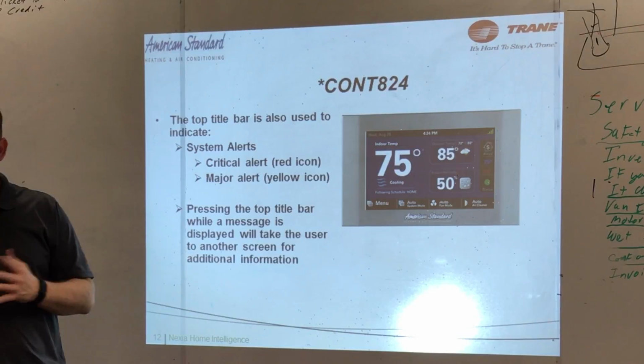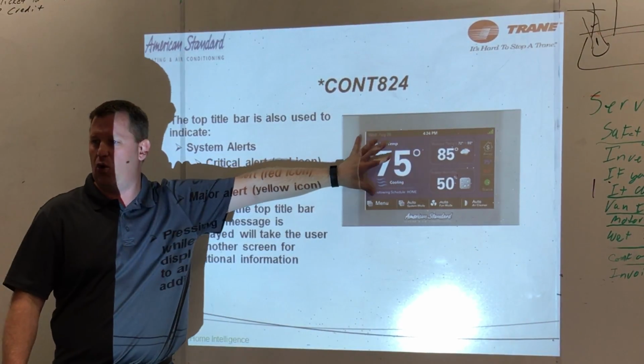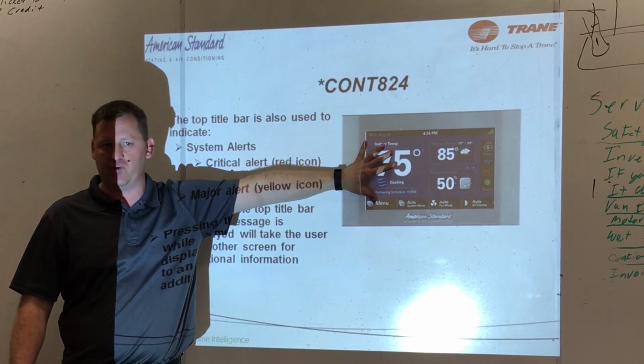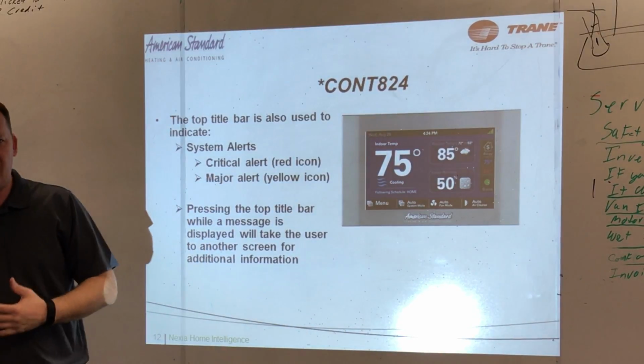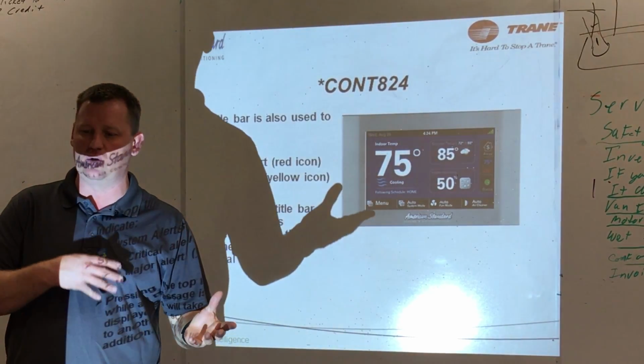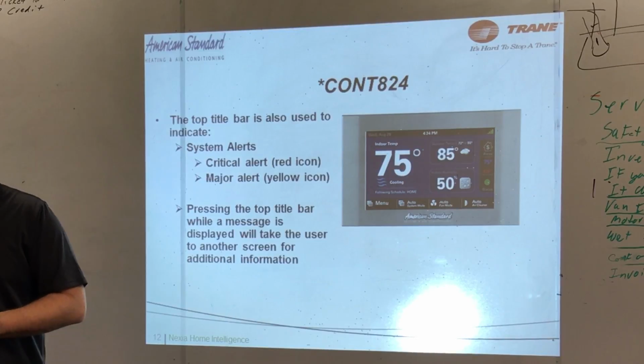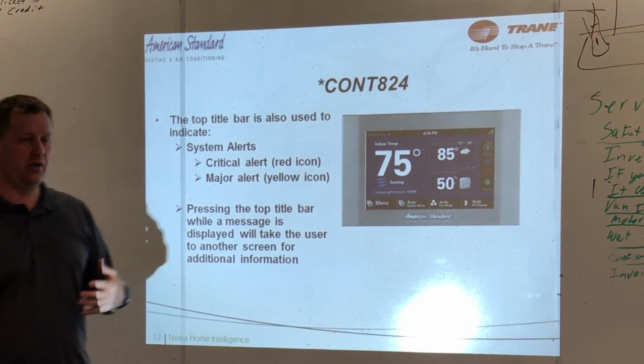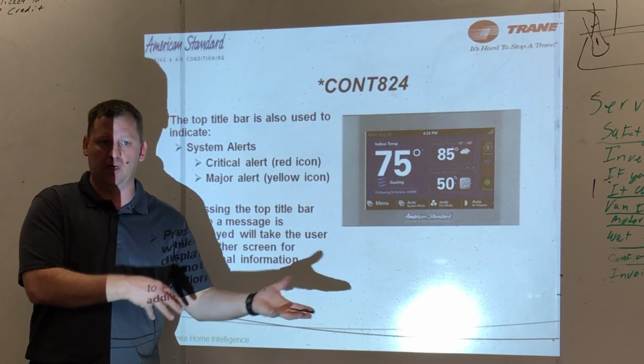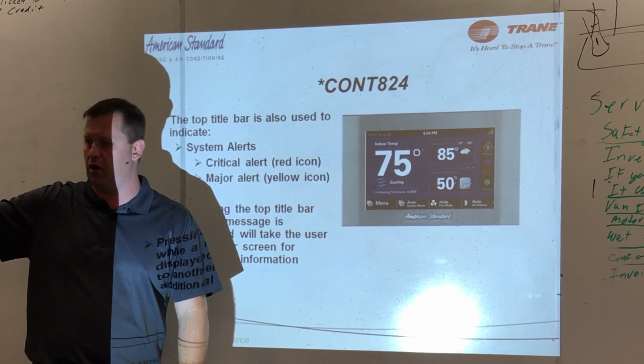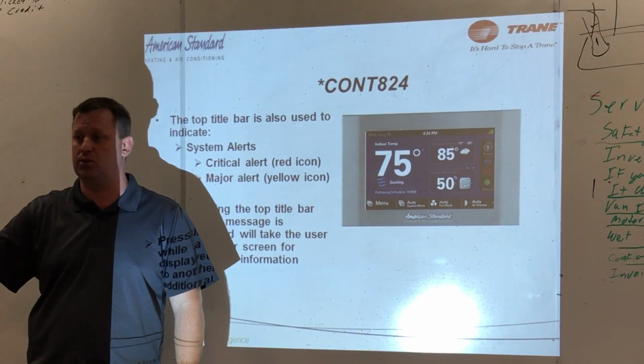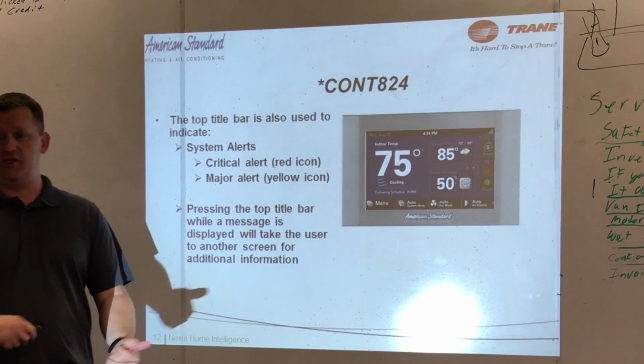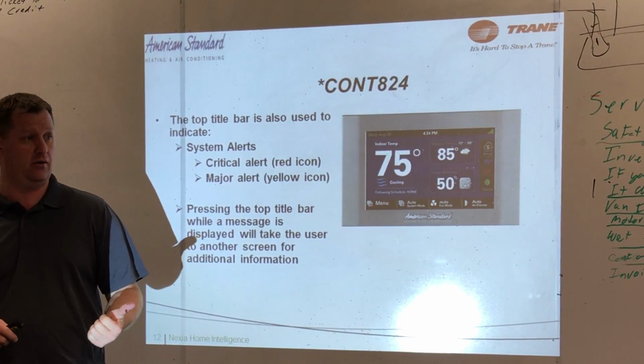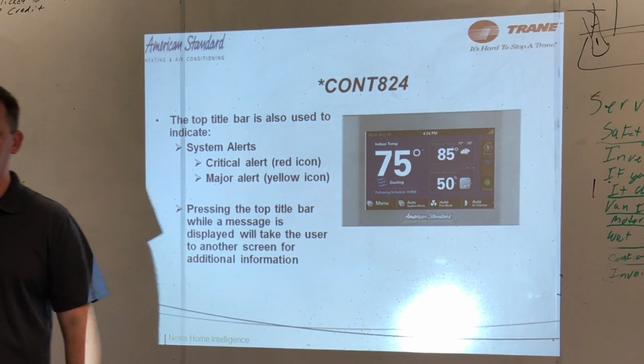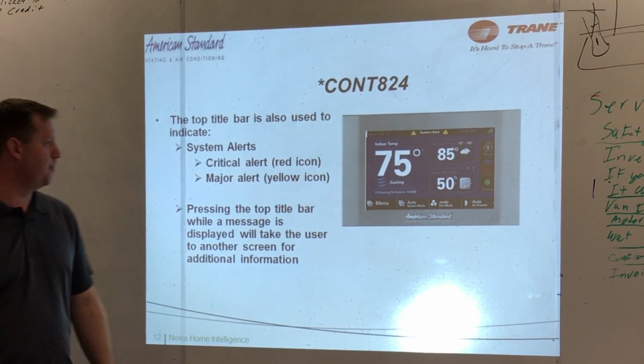With the 824, because it's not communicating, we don't have a whole lot of alerts we can really have. Outdoor stat or indoor temp sensor issues would be alerts that could happen. Indoor temp sensor failure would be a critical alert. Outdoor would be a major, because we've lost all our lockouts since we lost the outdoor temp, but we still have heating and cooling. If we lose the indoor temp sensor, we're just hosed, it doesn't know what to do, so that'd be a critical alert.